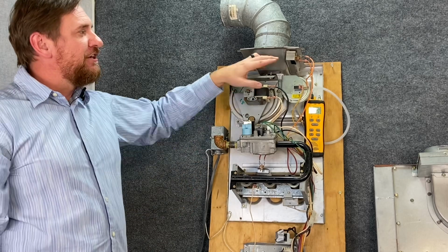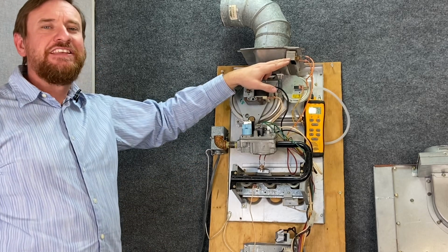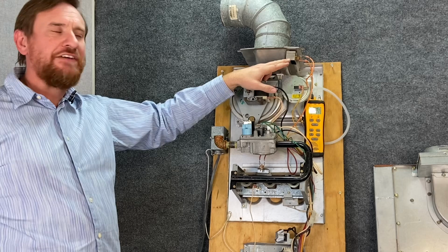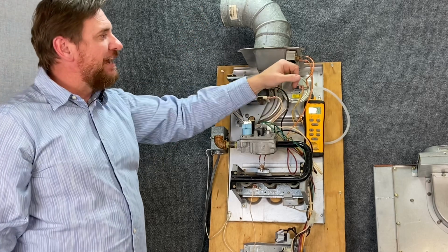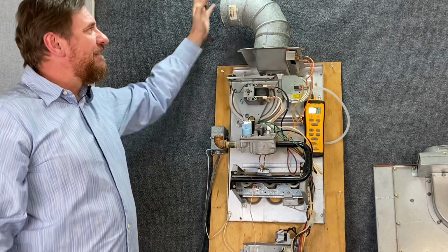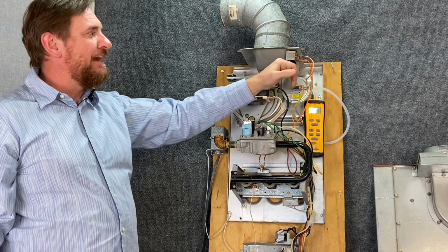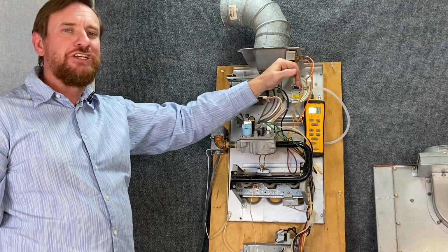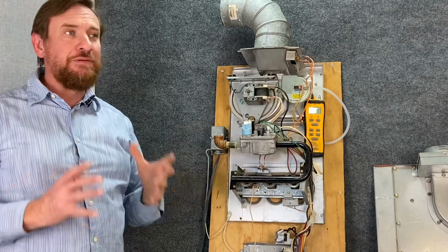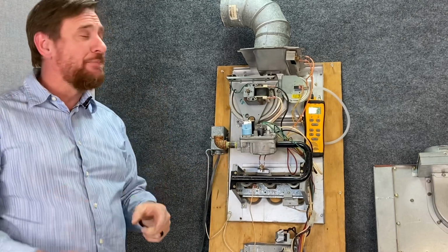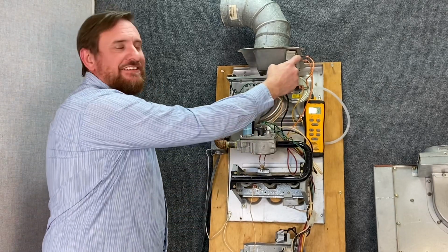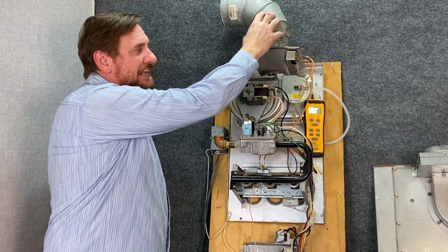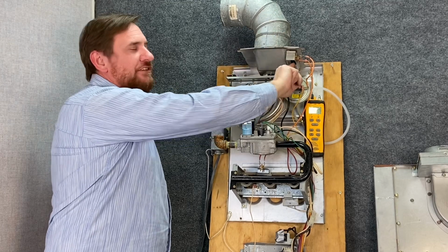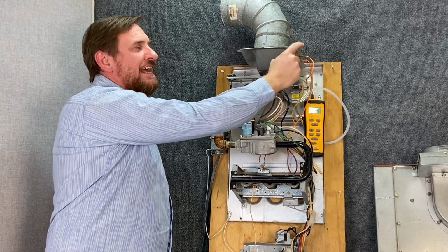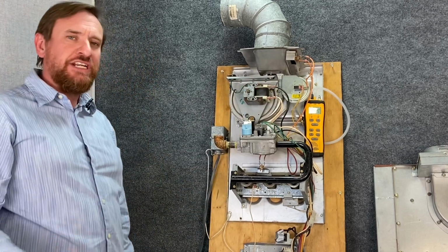A lot of manufacturers will have this. This is a draft hood connector or a draft hood limit. In this case, there's actually a hole inside of this. If the gas pressure backs up, it will start leaking carbon monoxide and combustion gases across this, which you think, oh my gosh, that's a problem. And yes, it is a problem, but the reason is we have this limit switch here. As these gases back up, it's going to push these hot gases across this limit switch, and this limit switch will trip, shutting the system down.